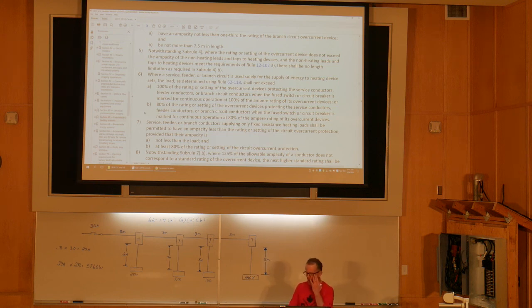All right, so imagine we're going to use a 30 amp breaker. We can only load it to 80%. So 0.8 times 30, that'll give us 24 amps. We'll make these heaters 240 volt. So 24 times 240, that would give us the 5,760 watts of heat that we could put on the branch circuit. So I run my number 10 out to the thermostats in the individual rooms, and then I'm going to drop off and pick up the heaters in the individual rooms.